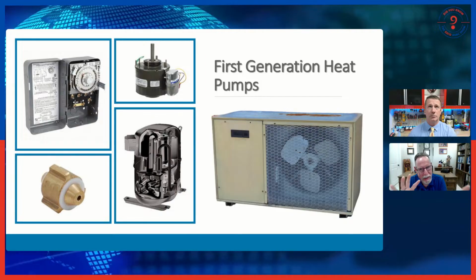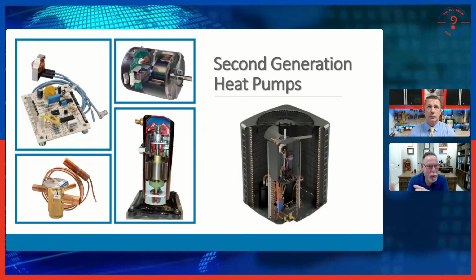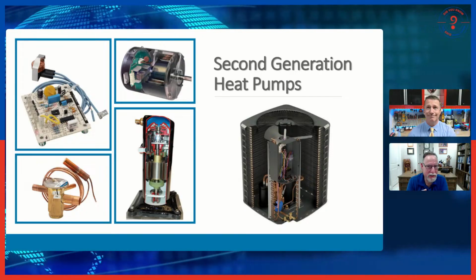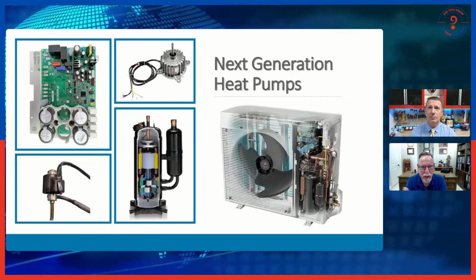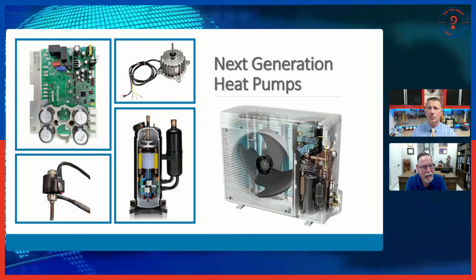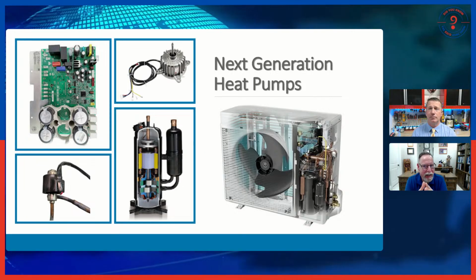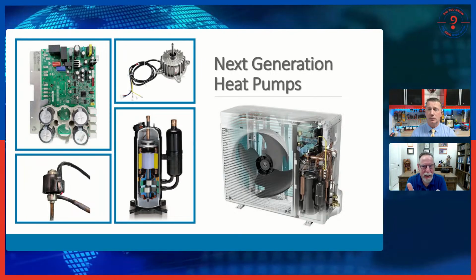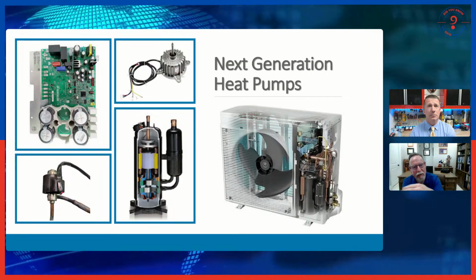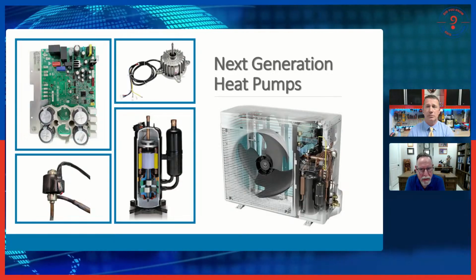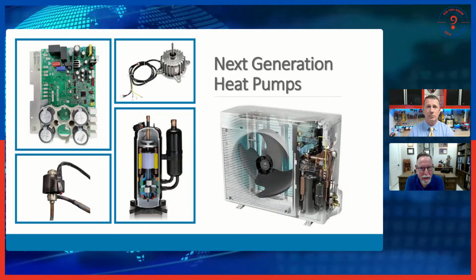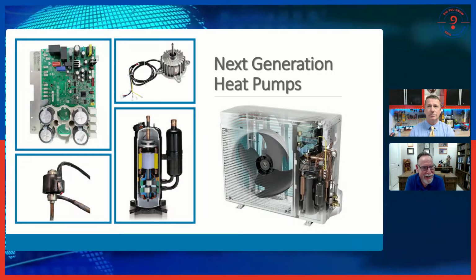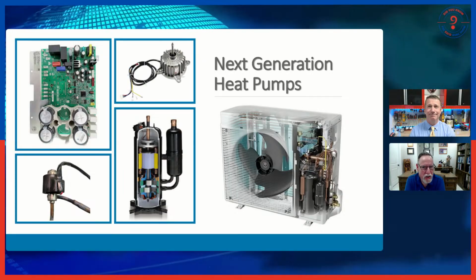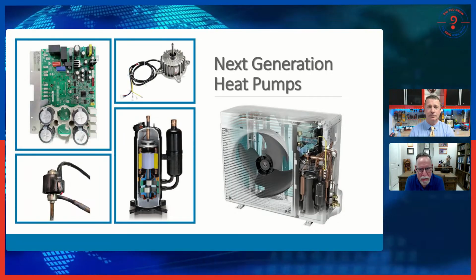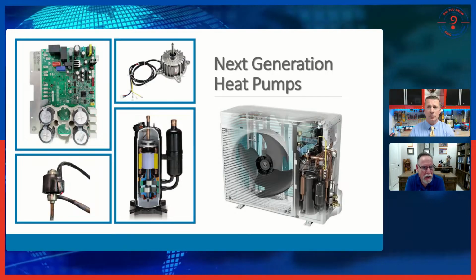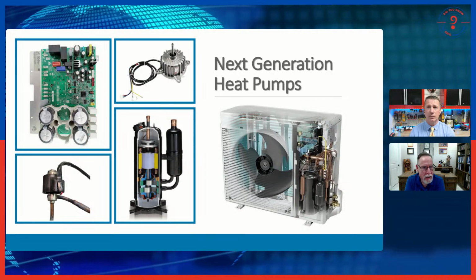So again, transitioning from these on and off, these 2-speed heat pumps - on off, I guess off is a speed - to our newer generation heat pumps, really night and day. Picture a system that ideally would turn on one time. The system would really never need to turn off, and it would simply gradually ramp up and ramp down in speed to maintain the desired set point, in a process that we didn't know what was called back in the 80s: load matching. The system is actually matching the load. It's adjusting itself, it's thinking, and in some cases predicting what the needs of the space are and adjusting the controls accordingly. So it's actually kind of neat.